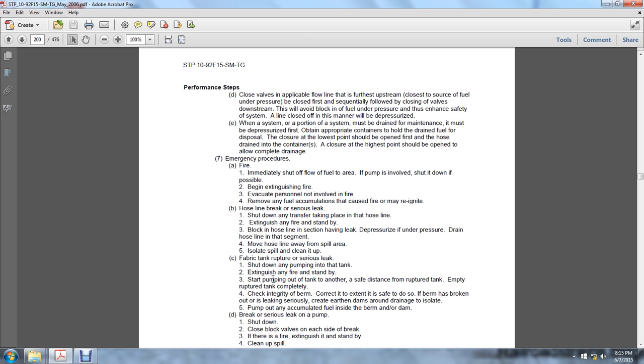Hose line break or serious leak. Shut down any transfer taking place in the hose line. Extinguish any fire and stand by. Block in the section of the hose line that has the leak. Depressurize it if under pressure. Drain the hose line in that segment. Move the hose line away from the spill area. Isolate the spill and clean it up.